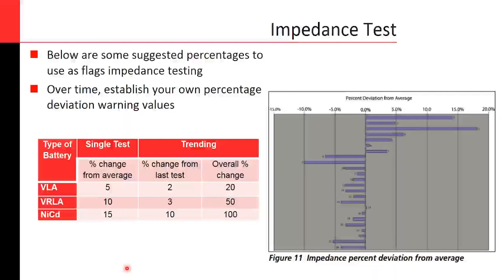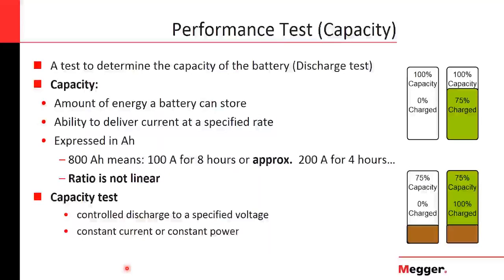Okay, so the next test is the performance test. The performance test is really a discharge test, in which you discharge the battery in a controlled manner with the only purpose of obtaining the capacity of the battery, how much energy the battery can store. The capacity is also the ability of the battery to deliver current at a specified rate. So this means that you need to use a constant current or a constant power to perform the test. This capacity is a nameplate value.